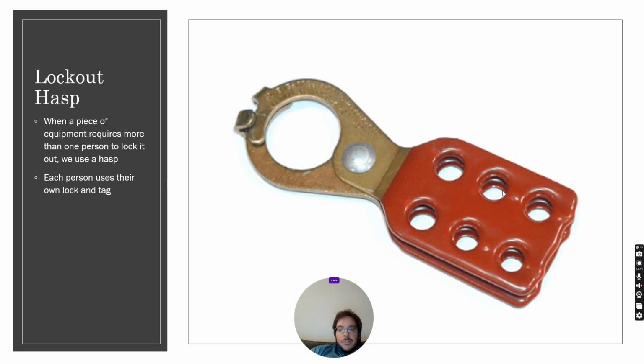Now, as I was talking earlier about lockouts, this is called a lockout hasp, and this one lets 6 different people lock out, because you can't put 6 locks on a switch. It's not going to fit. But what you can do is turn the switch off, and then this thing opens, it pivots on this rivet, and you can lock the switch with this in the circle here, and then each person can put a padlock in one of the holes, and then this thing will not open unless all 6 locks are removed, or as many locks as are on here. This gives us the ability for 6 people to work on the equipment and lock it out.